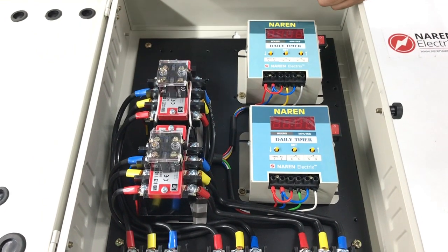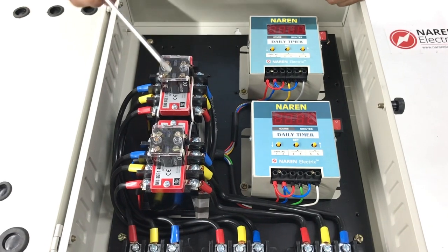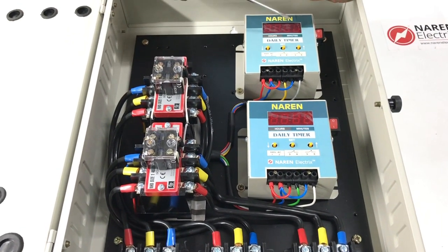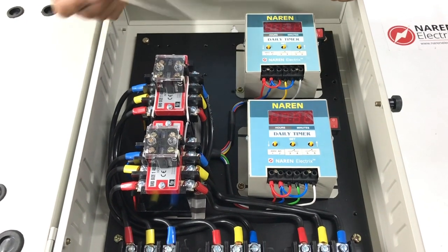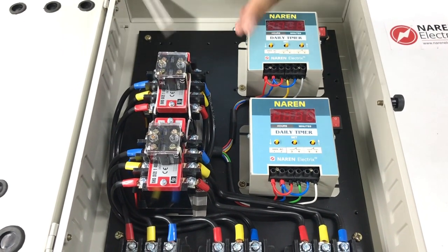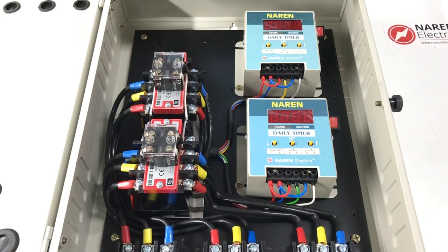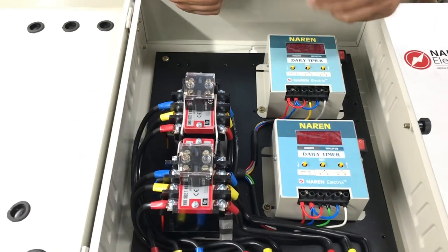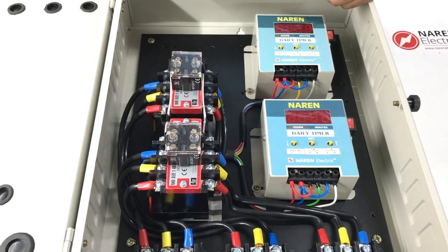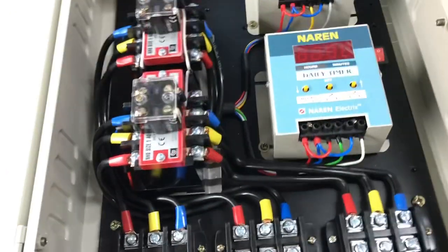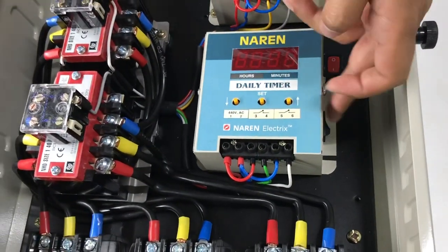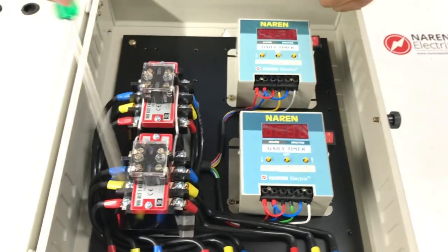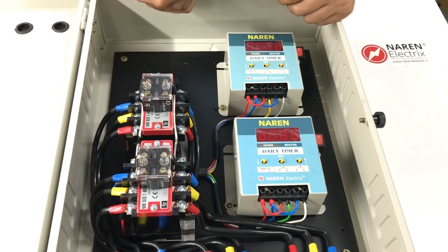Based on the corresponding time frame, that particular meter would be turned on, and the load will be fed through that meter. As a safety mechanism, we've used interlocking. Even if both daily timers turn on together, only one contactor will hold. Both contactors will not latch at the same time. Also, if he wishes to use only one meter for any reason, we've given a manual switch, so they can turn off both daily timers and switch on a particular switch so that the load is always drawn through one particular contactor.